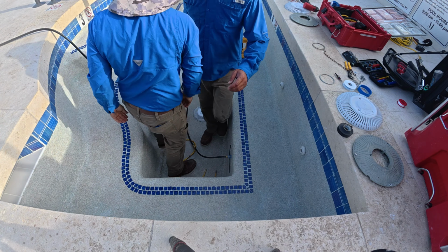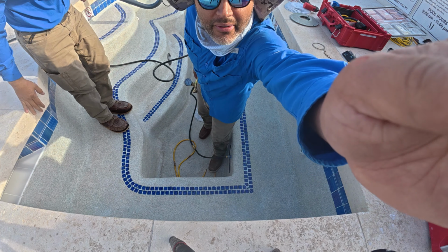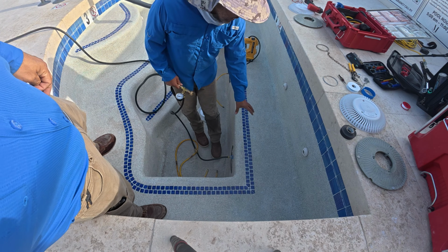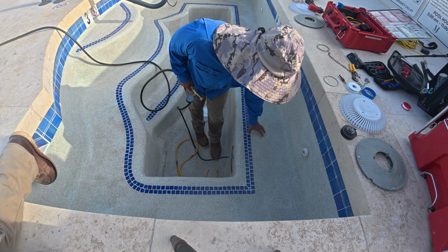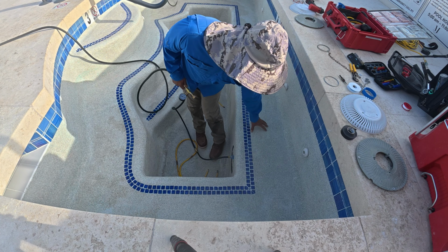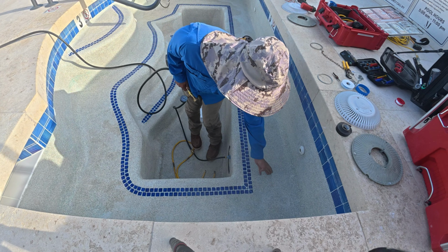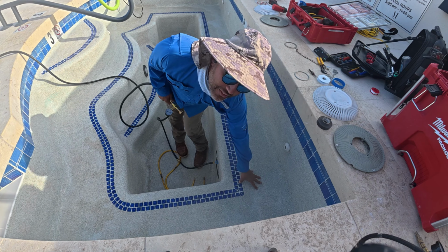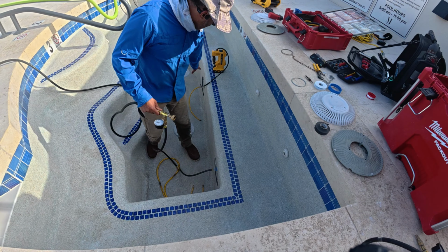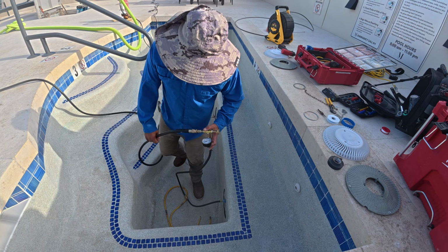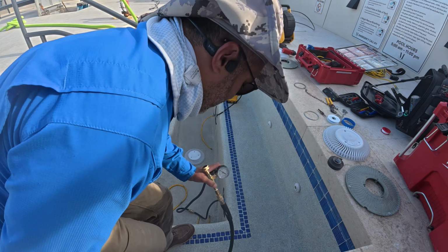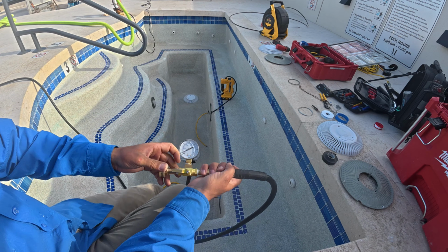Great. So we're at a pretty critical point now where we tested the whole line, and from there we know that there's a T right here, and then there's a coupling right here. So we're just literally going to test the T. We put an air plug on this side, and we already tested this whole line. So we're going to add pressure, and I think the moment of truth might come. You'll be able to witness it with us.